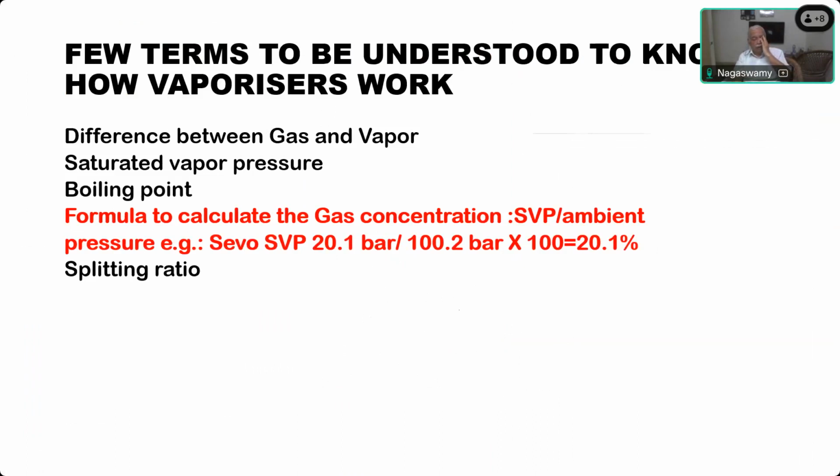On the contrary, when you want to anesthetize the patient and keep him unconscious, then you start using the vaporizer, keeping it at say 2%, 1%, 0.5%, depending upon the depth of anesthesia that you want to maintain. Then what happens? The fresh gas flow coming from the flow meter, part of it will go into the vaporizer, pick up the vapor of the agent, and then come and join at the outlet level with the fresh gas flow that is coming in. So you can vary the percentage of fresh gas flow entering the vaporizing chamber or avoiding the vaporizing chamber and going straight by a bypass channel.